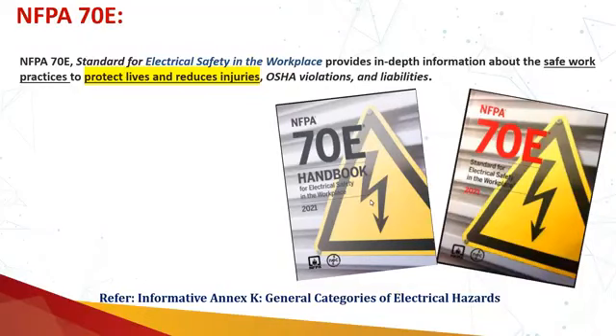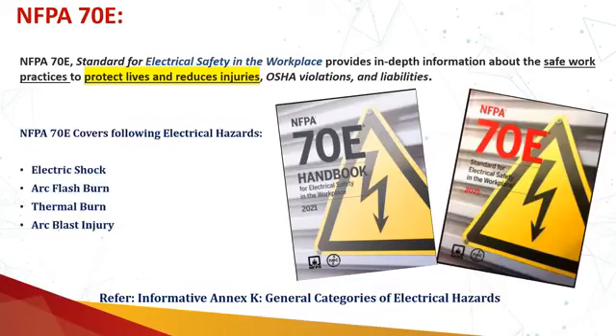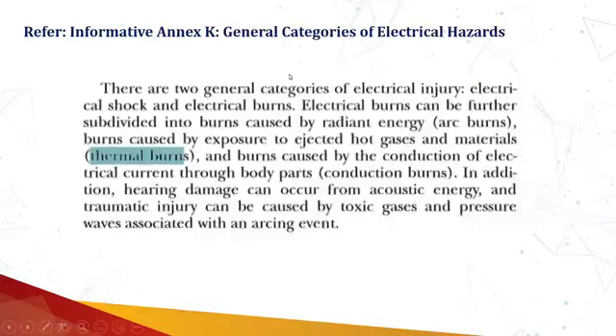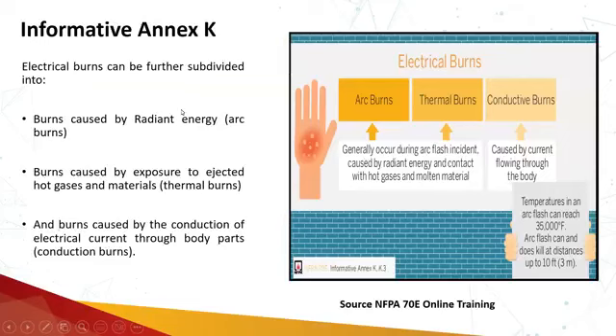So if we look into this Annex K, there you are going to find some general categories of those electrical hazards. So what are those categories? There are four categories: electric shock, arc flash burn, thermal burn, and arc blast injury. If we look into electric shock, we know that electric shock is due to the passage of the current through the body. And due to that passage of current, an electric burn is created, which is called a conductive burn. So this burn is caused by the current which is flowing through our body.